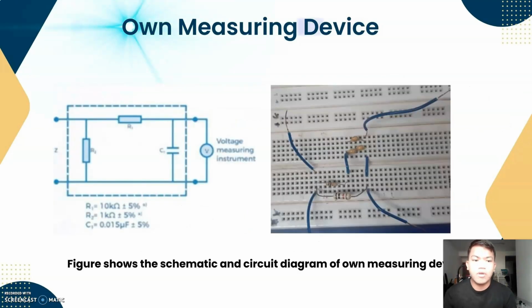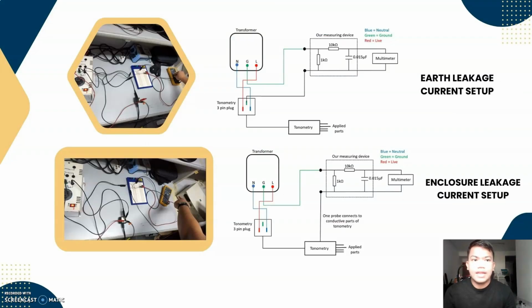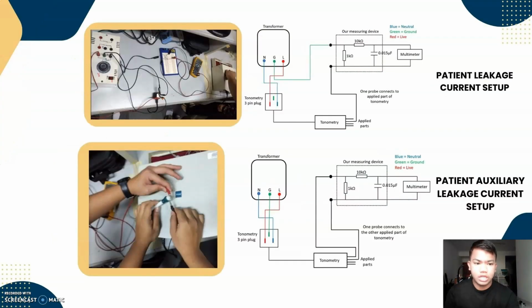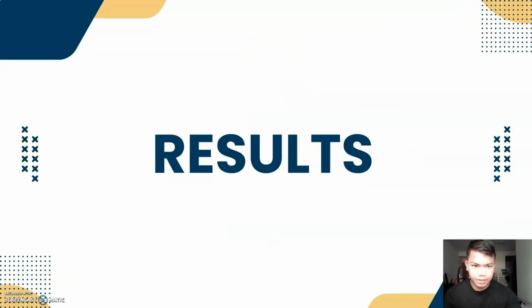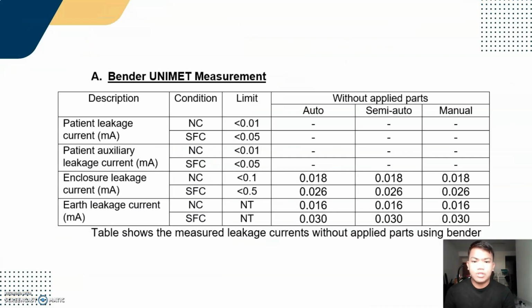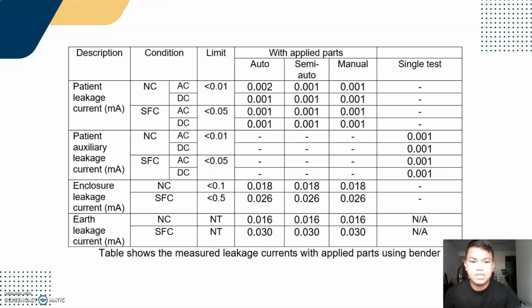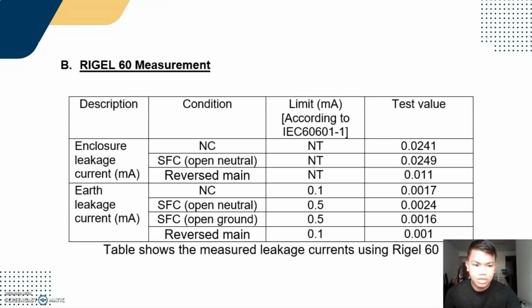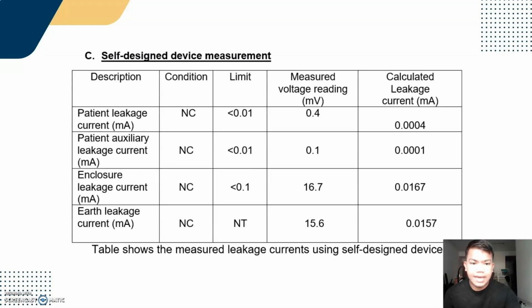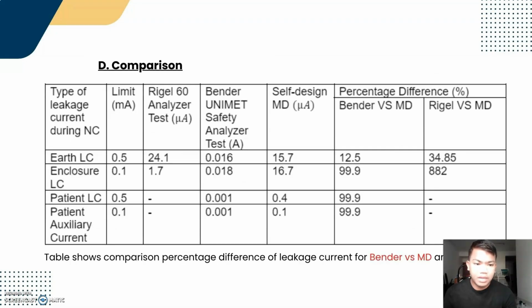This is the circuit diagram of our own measuring device. And this is the current setup for earth leakage current, enclosure leakage current, patient leakage current, and patient auxiliary leakage current. For results, this table shows the measured leakage current using Bender without applied parts. This is for with applied parts. This is for the measured leakage current using Rigel 60 and using our self-designed device. This is the comparison between Bender, Rigel, and our own measuring device.